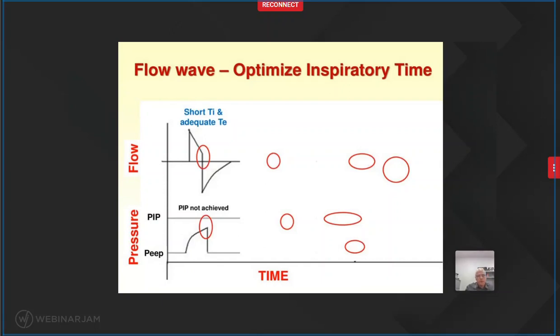So here we have on the top flow, on the bottom pressure. When the TI is too short, like here, you can see that the inspiratory flow does not reach baseline when the expiratory flow begins. So expiration begins before the inspiratory flow reaches baseline. The problem with that is that you did not have enough flow, therefore your PIP was not achieved. Okay, so you end up with lower PIP than you expected.